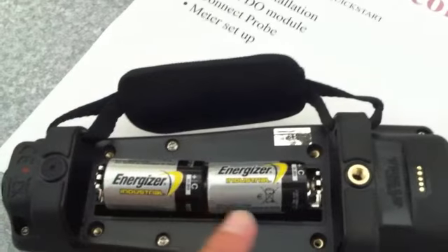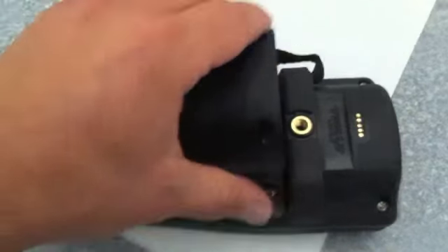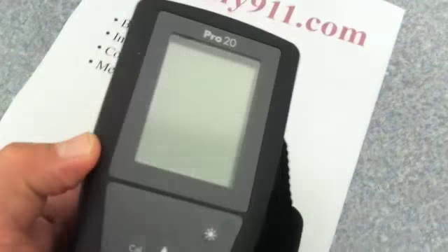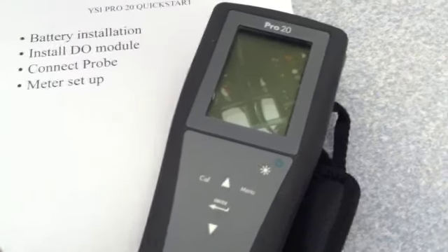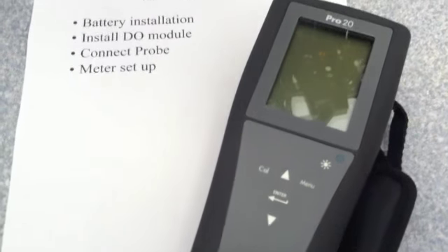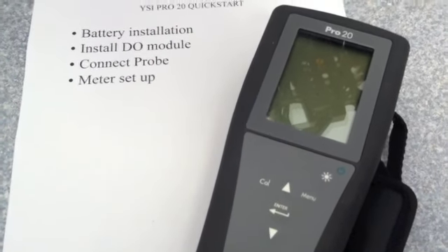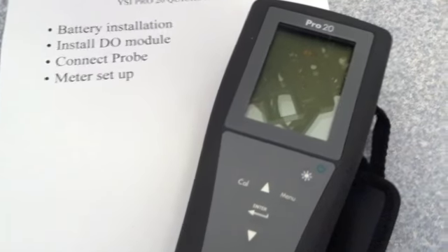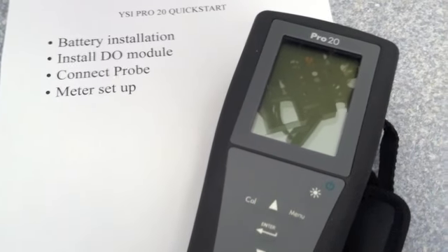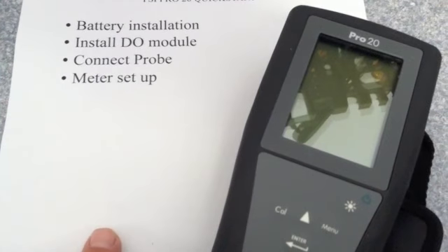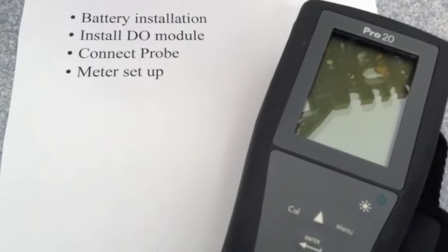And we've already installed the batteries. All we have to do is take the C's out of the package and put your cover back on, tighten the 4 screws, and then when you turn it over, when it powers up, you're going to be able to just hit the check boxes for language. The sensor type, you probably will either have polarographic or the galvanic, and then you can hit the membrane type that you're using as well. And then once you do that, we'll continue on with installing the DO module.